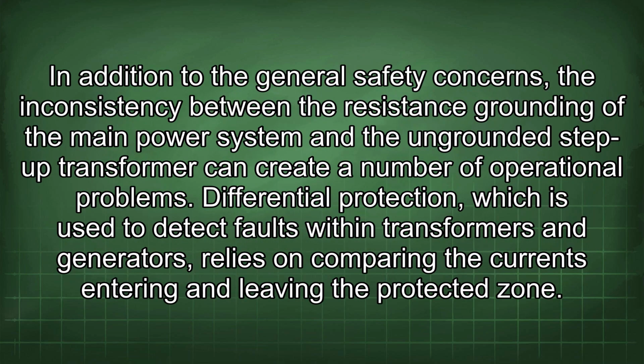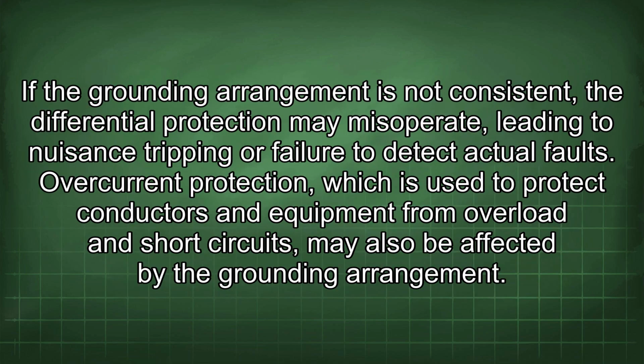In addition to the general safety concerns, the inconsistency between the resistance grounding of the main power system and the ungrounded step-up transformer can create a number of operational problems. Differential protection, which is used to detect faults within transformers and generators, relies on comparing the currents entering and leaving the protected zone. If the grounding arrangement is not consistent, the differential protection may misoperate, leading to nuisance tripping or failure to detect actual faults.